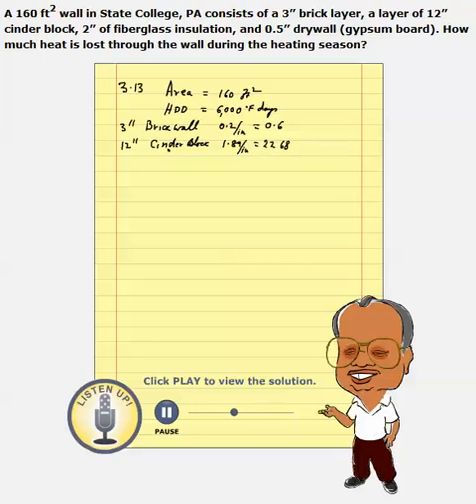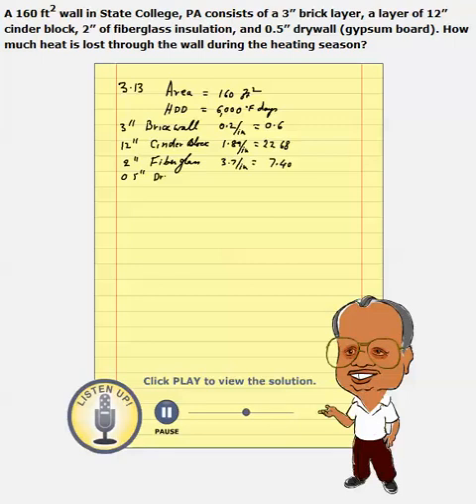And we have two inches of fiberglass, and fiberglass provides per inch an R value of 3.7, therefore two inches would be 7.40. And now we have, finally, half inch drywall, and the whole half inch of drywall will provide us an R value of 0.45. So together, when you add all these layers up, the R value of the wall happens to be 31.13.